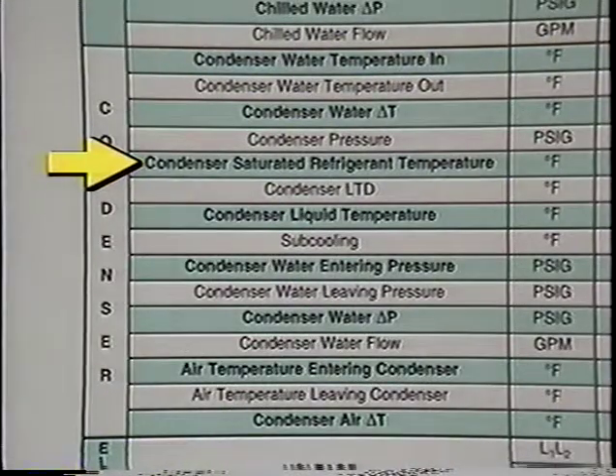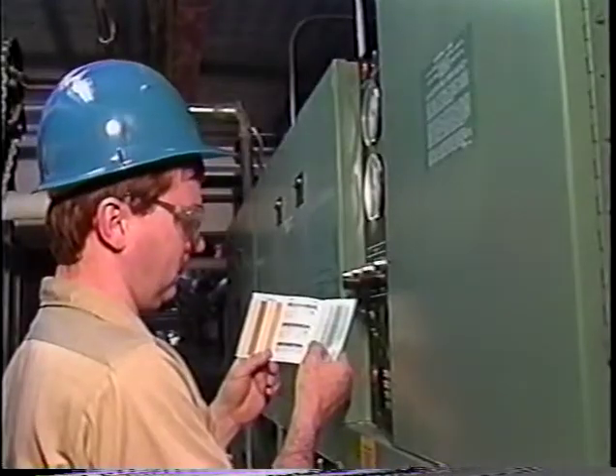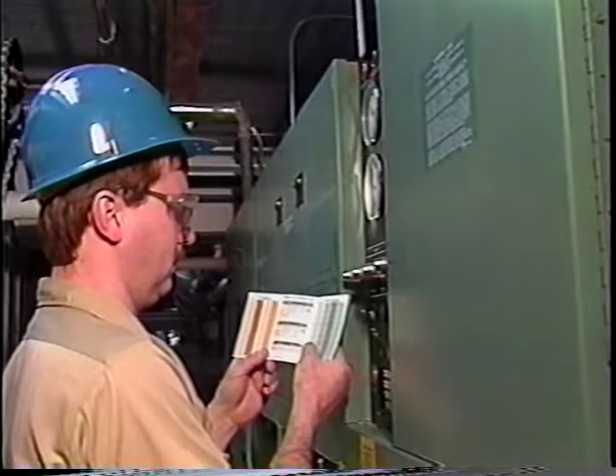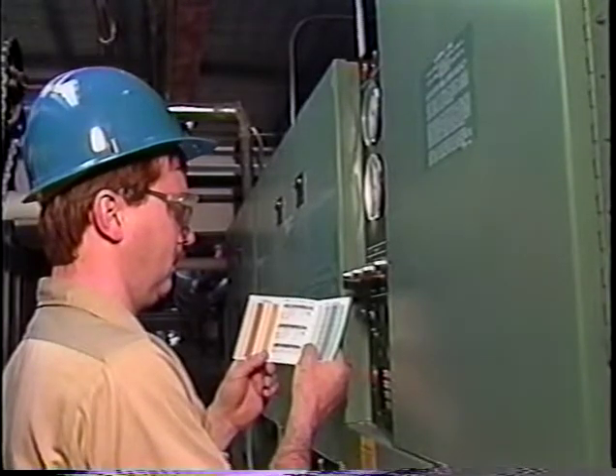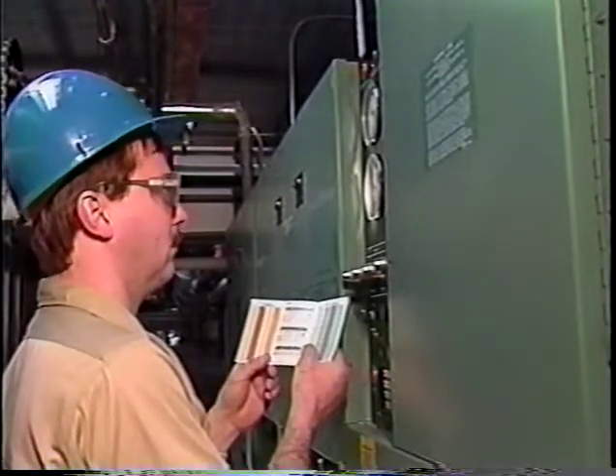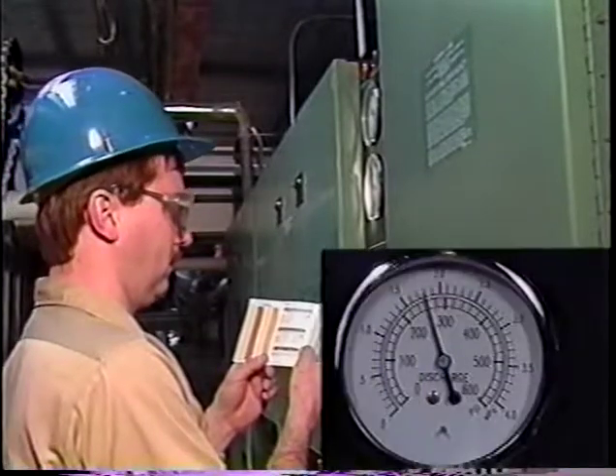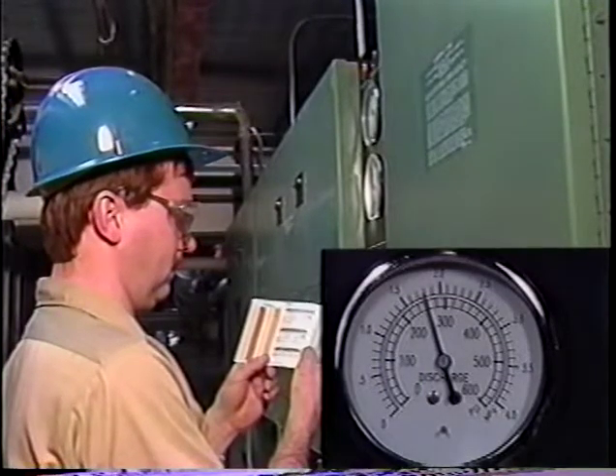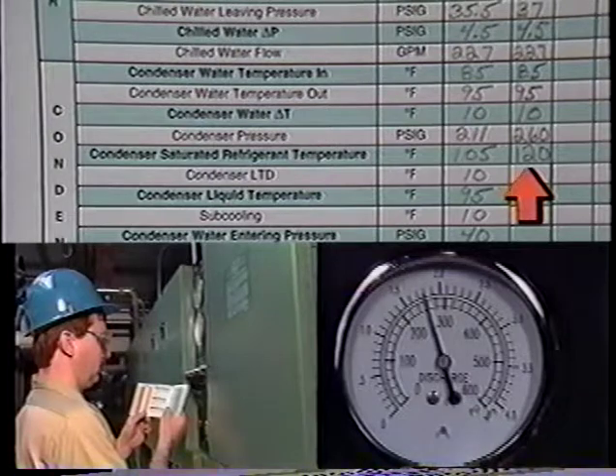Condenser saturated refrigerant temperature. On some chillers, the saturated condensing temperature may be read directly at the control panel. If this is not the case, then the saturated condensing temperature is found by using a pressure temperature chart to convert the condensing pressure to a temperature reading. This temperature is required for determining the condenser leaving temperature difference.